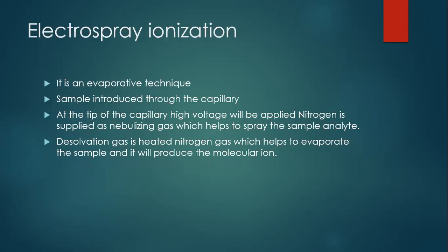Electrospray ionization is an evaporative technique. The sample is introduced through the capillary and the tip of the capillary has voltage applied. Nitrogen is supplied as a nebulizing gas which helps to spray the sample analytes. Desolvation gas, heated nitrogen gas, help to evaporate the sample and produce molecular ions.